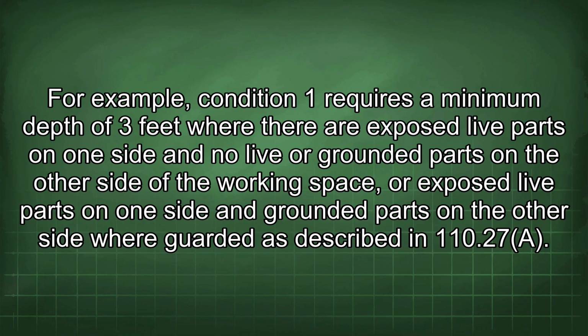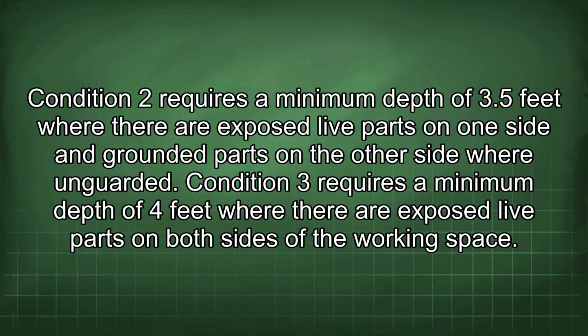For example, Condition 1 requires a minimum depth of 3 feet where there are exposed live parts on one side and no live or grounded parts on the other side of the working space, or exposed live parts on one side and grounded parts on the other side where guarded as described in 110.27(A). Condition 2 requires a minimum depth of 3.5 feet where there are exposed live parts on one side and grounded parts on the other side where unguarded.